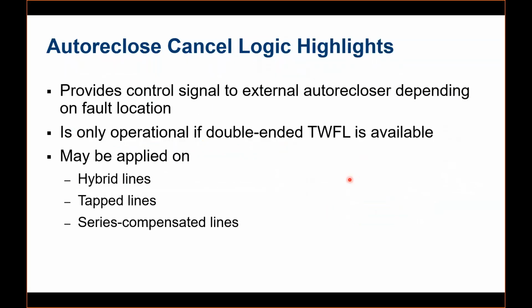It uses the double-ended fault location method, because whenever a fault happens in that particular portion that you have already defined, the relay already knows the fault location precisely, and you can just define that portion with a tolerance to block the auto recloser. The auto recloser can be external, so you can just send a blocking signal to your external auto recloser, and you can control it according to the fault location. It is applicable for hybrid lines, tap lines, and it's also good for series compensated lines if you have capacitors.